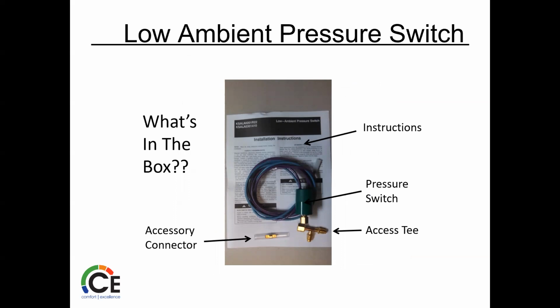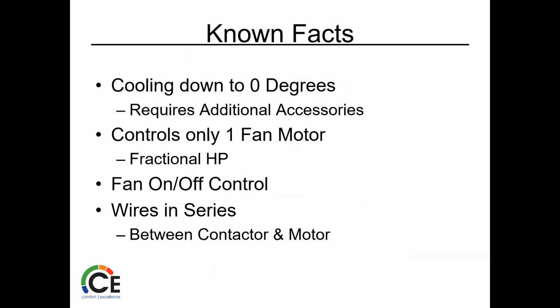The old faithful, right? Just the basic low ambient switch, a 2-wire switch, hooks right on your service valve. It comes with a T to make that happen, so you can still hook up your gauges and check pressures. This one only cools down to 0. Does require some additional accessories, a winter start kit usually. It can only control one fan motor, it just has 2 wires. Basically turns it on or off depending on the pressure. If it opens, it shuts the fan off. Once it closes, it brings it back on. Wires in series.